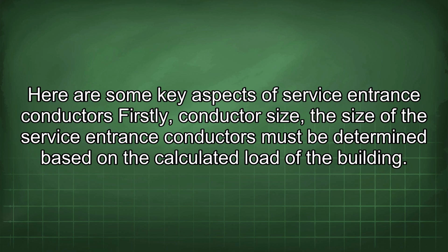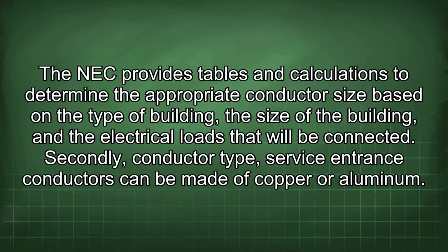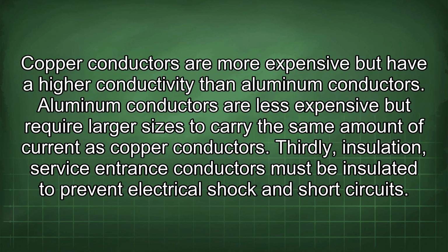Here are some key aspects of service entrance conductors. Firstly, conductor size. The size of the service entrance conductors must be determined based on the calculated load of the building. The NEC provides tables and calculations to determine the appropriate conductor size based on the type of building, the size of the building, and the electrical loads that will be connected. Secondly, conductor type. Service entrance conductors can be made of copper or aluminum. Copper conductors are more expensive but have a higher conductivity than aluminum conductors. Aluminum conductors are less expensive but require larger sizes to carry the same amount of current as copper conductors.